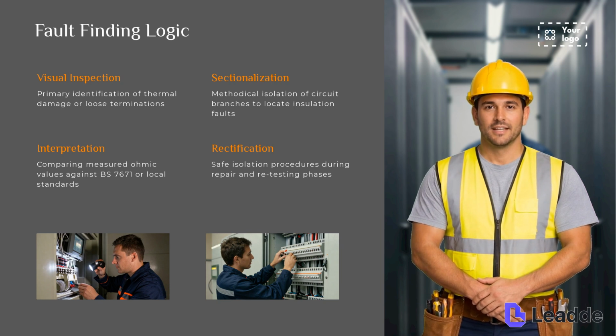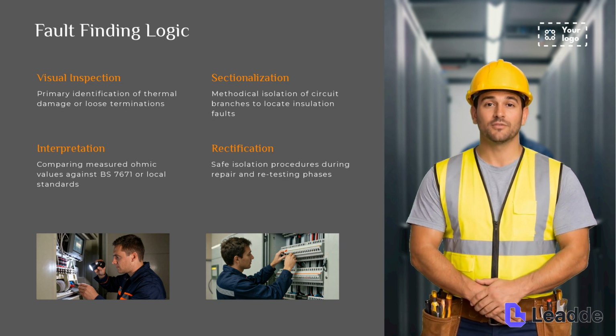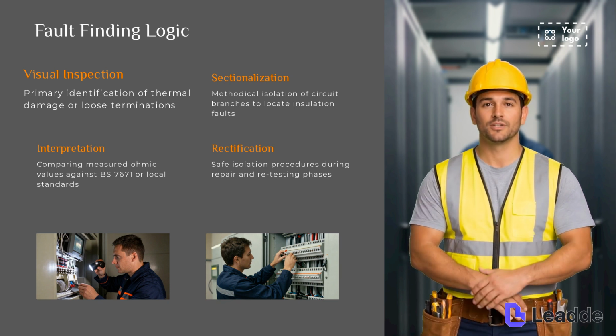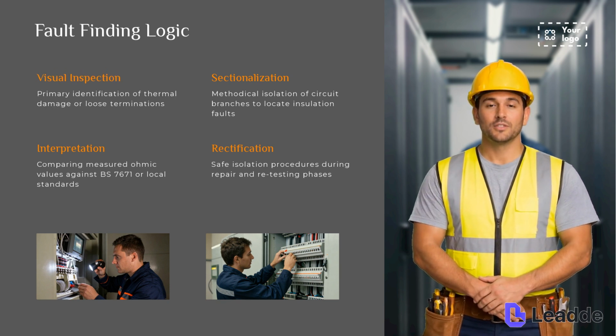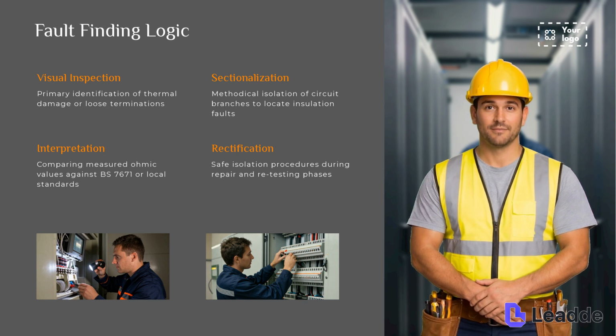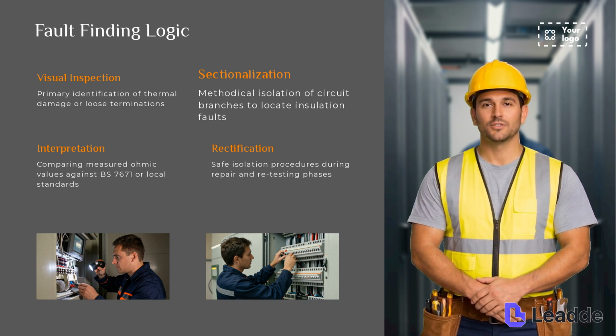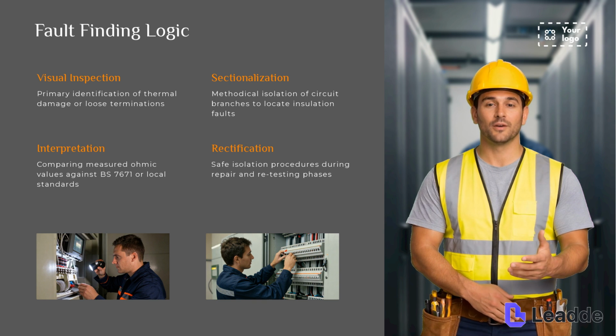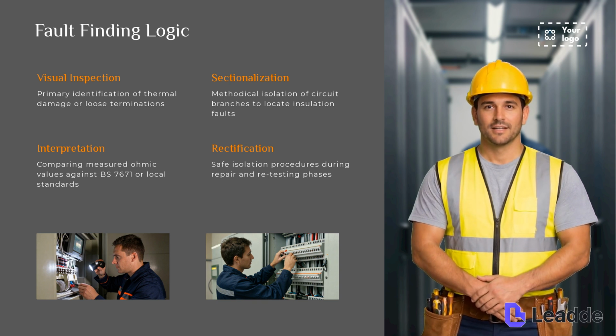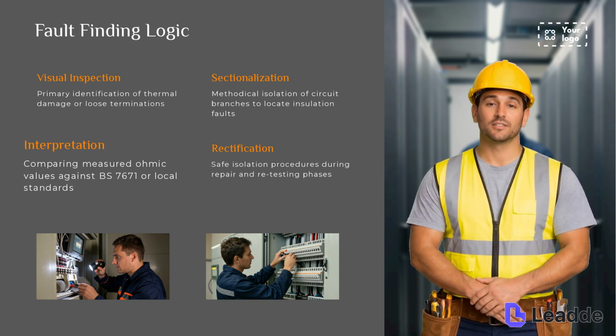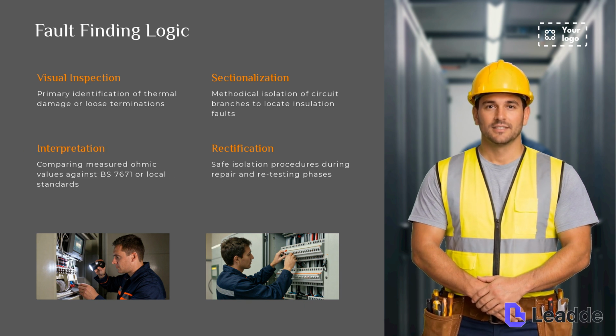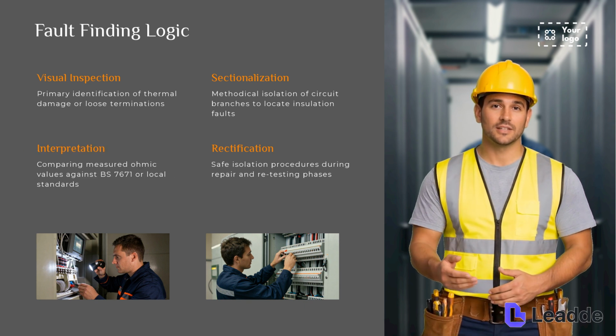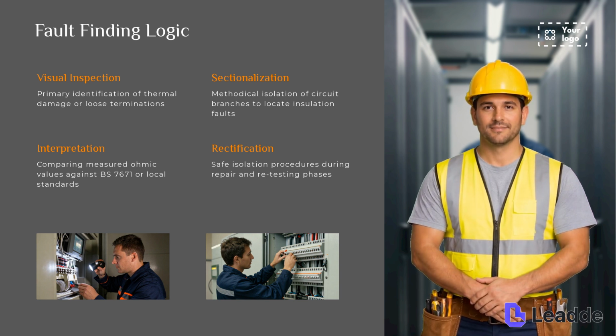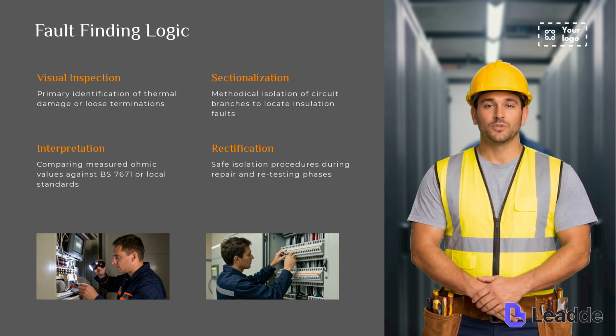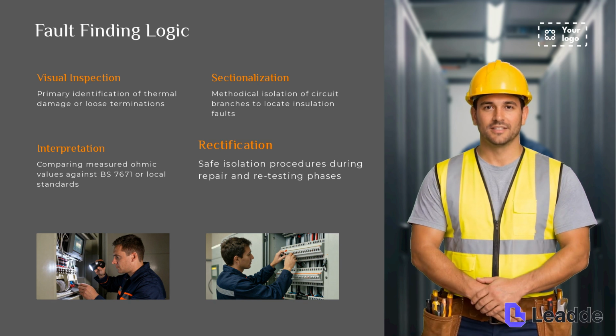The process begins with a visual inspection to identify primary issues like thermal damage or loose terminations. This is followed by sectionalization, a methodical isolation of circuit branches to locate insulation faults. All findings must be interpreted by comparing measured ohmic values against the standards set in BS 7671 or relevant local regulations. Finally, safe isolation procedures must be followed during the rectification and subsequent retesting phases.